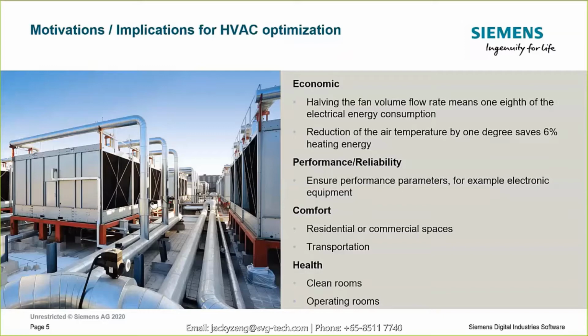Take a system that uses fans to drive flow. If you can cut the volume flow rate requirement of the system in half, meaning the fan would only need to supply half the flow rate, you would reduce the electrical energy consumption of that fan by 7/8. So it would require only 1/8 of the original energy to drive the fan.